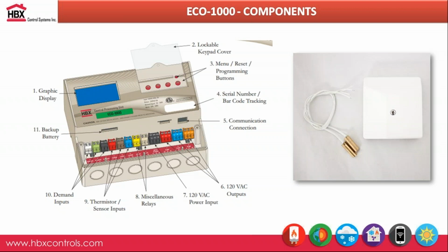We also have numerous thermistor and sensor inputs, so you could have a sensor for your hot tank, cold tank, as well as run an outdoor sensor to these units to provide outdoor reset for your hot tank on the 1000 controller. You have miscellaneous relays, which are used for your first and second stage of your heat pumps, and then 120 just to power up the unit itself.